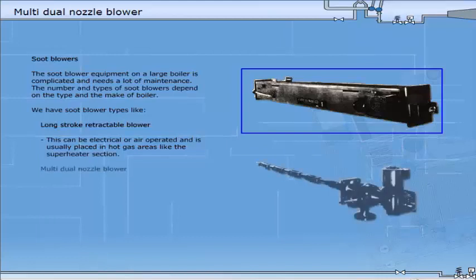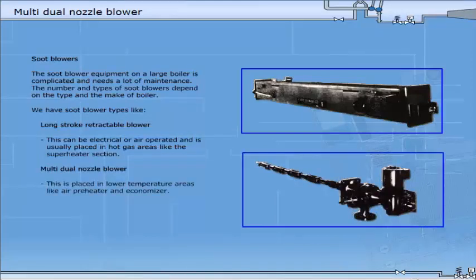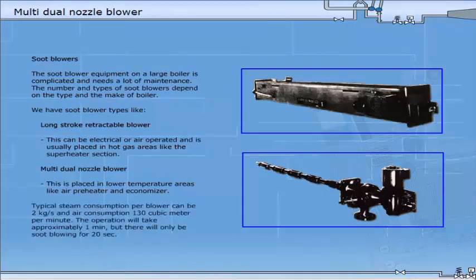The multi-dual nozzle blower is placed in lower temperature areas like air preheater and economiser. Typical steam consumption per blower can be 2 kilos per second and air consumption 130 cubic meters per minute. The operation will take approximately one minute, but there will only be soot blowing for 20 seconds.